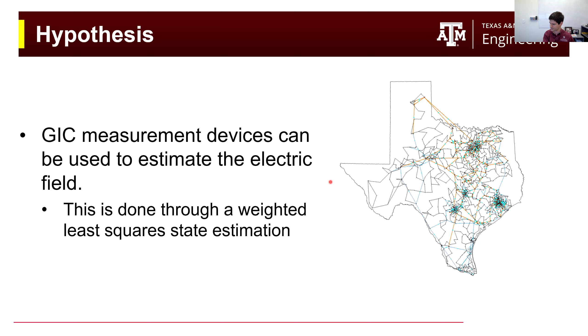Therefore you could say these substations, the grounding on these substations has a very high impact on the results of the system. So you should send some techs out there to do a fall-of-potential measurement to calculate the updated substation grounding resistance. Or we need to go try to find the old papers on this transformer, or go out there and put some Rust-Oleum on the nameplate to figure out more information about this transformer, like what core type it is, whether it's core form, shell form, etcetera.